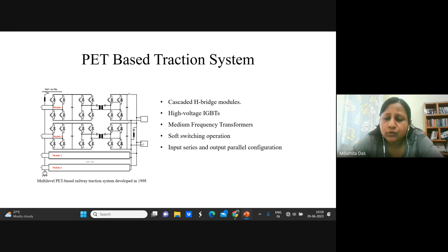This medium frequency transformer was actually developed at EPFL, Switzerland. They have shown that the transformer shown in A is a 36.3 kVA medium frequency transformer, and in B a 400 kilowatt test rig is shown for this railway application.